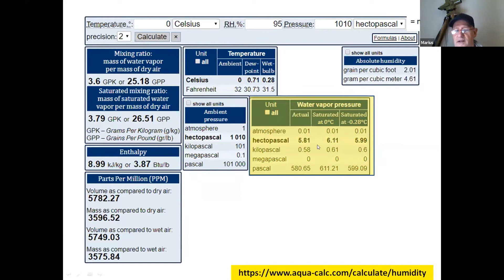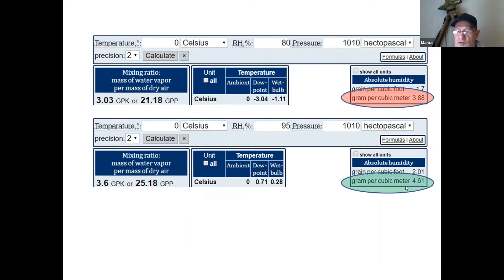Okay, so going back to that other example with a temperature of 0 Celsius, 80% humidity, which is not great for the cold room, versus 0 Celsius, 95. The absolute humidity in grams per cubic meter, you get the two values there. And then obviously this is the 95 where we want to be. And then you can get systems where you say, fine, if my poor cold room is running at 3.88 grams per cubic meter of cold room space, and I actually want this good scenario of 4.61, the difference between the two is only 0.73 grams of water per cubic meter of cold room space.